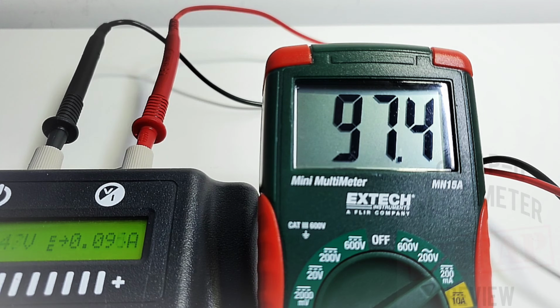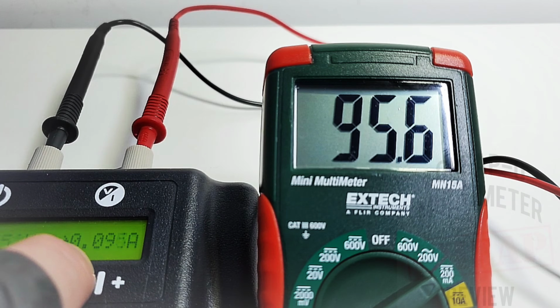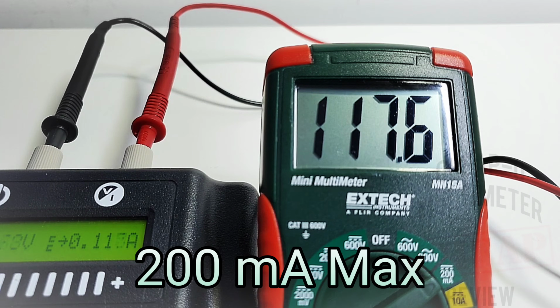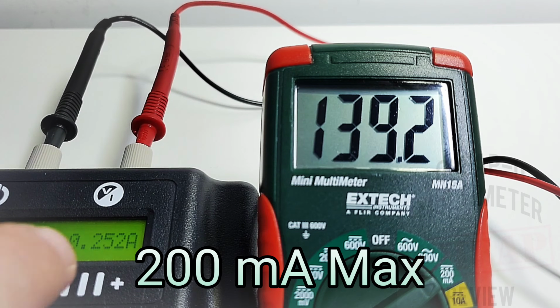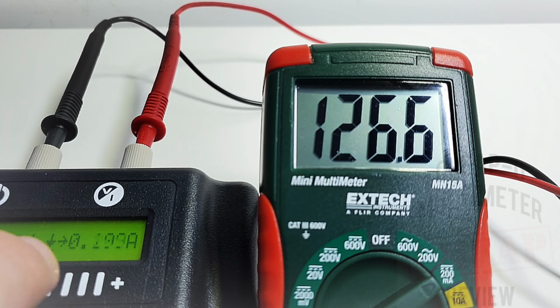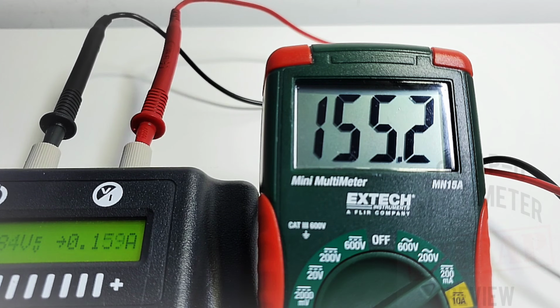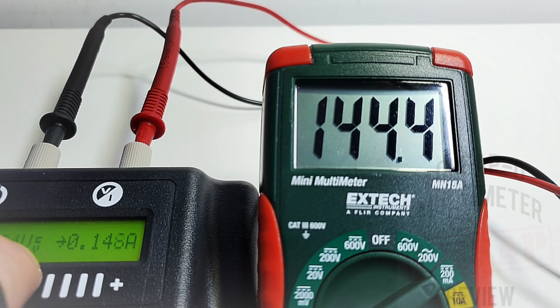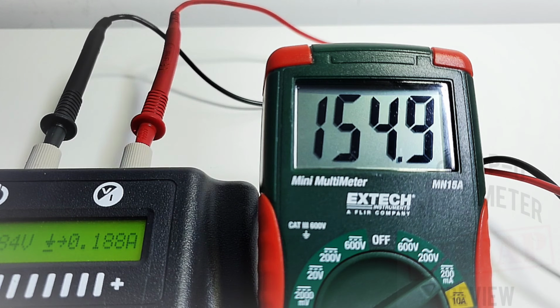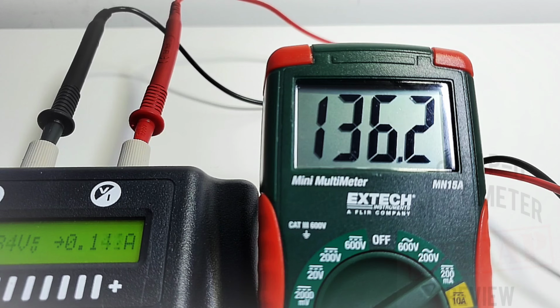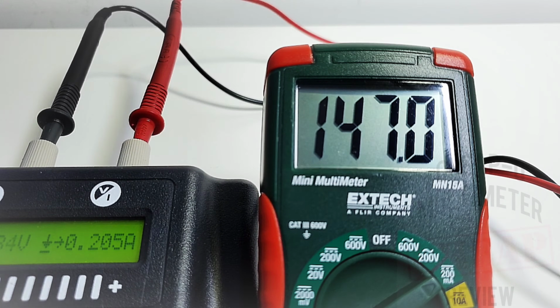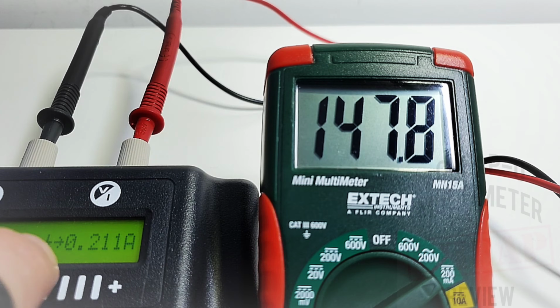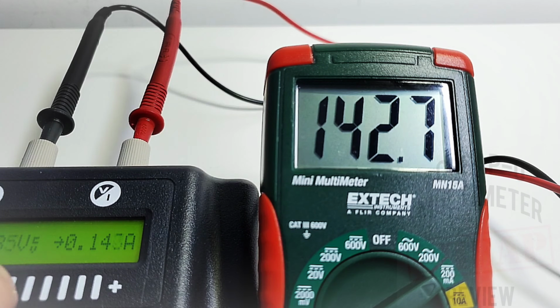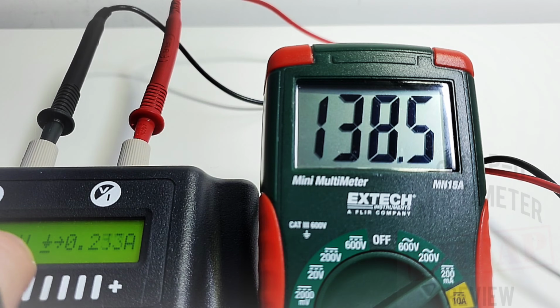Take that up to just under 100 milliamps. 95, 97, 116 milliamps right now, and pretty well spot on the EXTECH. And let's see here. 200 milliamps spot on, and isn't that interesting? We're sitting at around 150. So it kind of went down. Let's see, can we get a little bit higher, a little closer? 188 milliamps. Doesn't want us to get that close. 205, nope, coming back down. Isn't that weird? For some interesting reason, I cannot go any higher than about 150 milliamps.